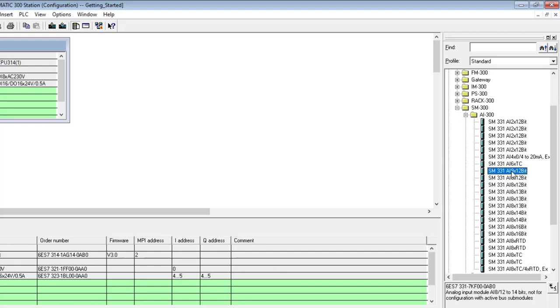For example, a 12-bit card will be less sensitive compared to a 16-bit card, which implies that when I apply a signal to a 16-bit card, it will be able to pick up the slightest change in the signal, whilst a 12-bit card will struggle to pick up that same change. So in other words, the higher the resolution or the higher the bits, the more sensitive the card is and the better it can detect the smallest change in your analog signal. With this understanding, we will now look at the next.